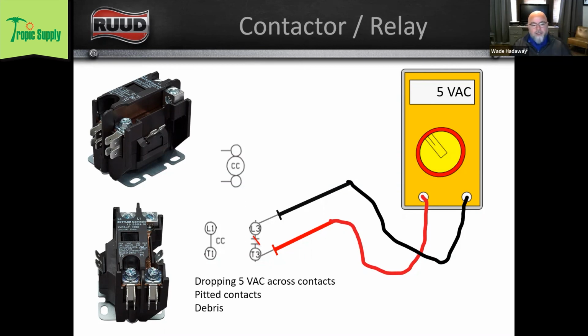And again, that could be because of pitted contacts or some debris in there, especially with older contactors that aren't sort of enclosed, right? Like an old school contactor that you can get to and see everything. There's all sorts of stuff that can end up inside a contactor that either makes the linkage not work smoothly or blocks the contacts from making good contact.